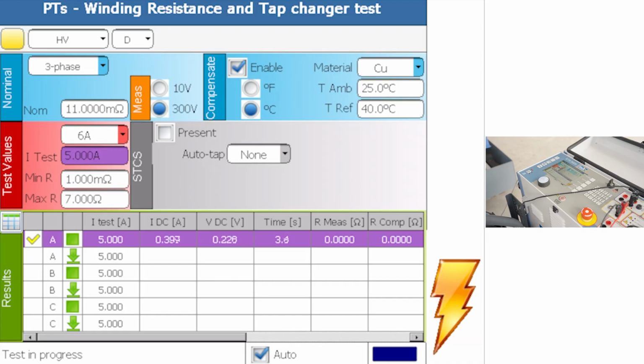What we are seeing right now is the current, which is rising, and the voltage, which I'm measuring. This can take between 1 or 2 minutes, because what we want is for the voltage drop to stabilize so that we can have an accurate measurement, because the winding, which we are measuring, has this characteristic of opposing the change. As soon as there is any change of current, it generates a certain voltage, so we want to have a stable voltage measurement to be able to say that we have measured the correct resistance. And we can already see that the resistance being measured, let it stabilize a little bit, is about right now 8 milliohms, but let it go to 5, which it did now, and let's see how this will finish.